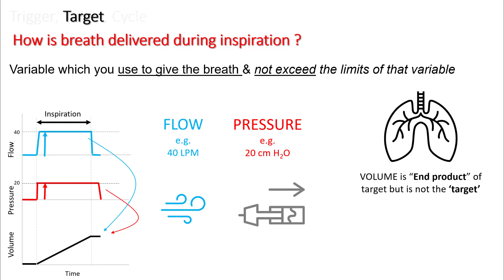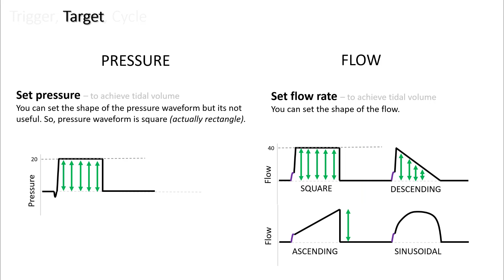So if you set a pressure target, for example 20 centimeter of water, that 20 centimeter of water will persist till the cycling phase begins. The same thing happens with the flow rate. The flow rate, however, comes in different shapes. You can either have a square waveform or a descending waveform. There have been other waveforms that have been studied, like ascending and sinusoidal, but these were not found to have any benefit, so they are no longer used.